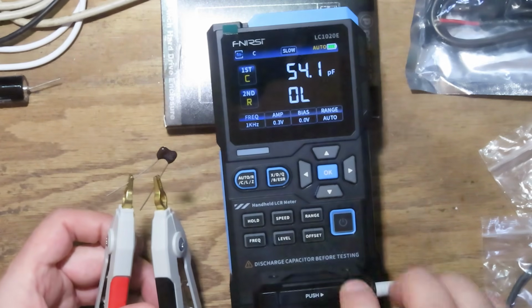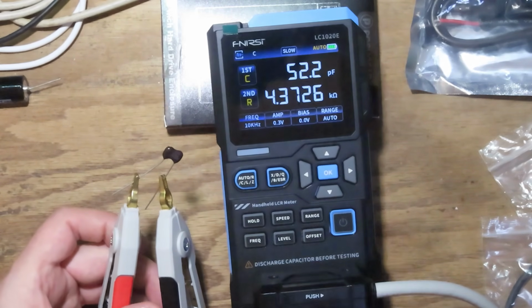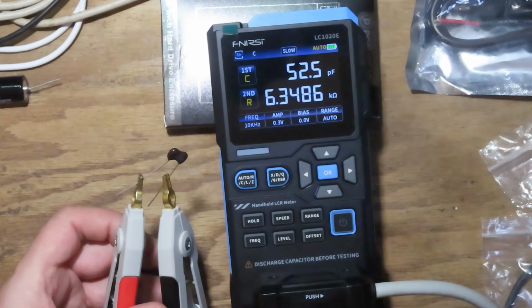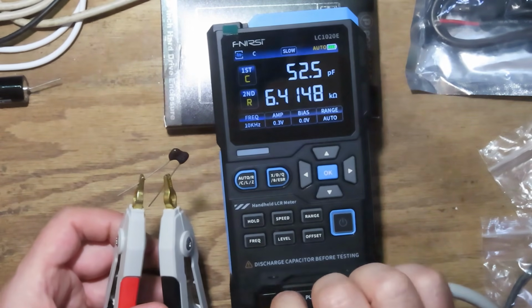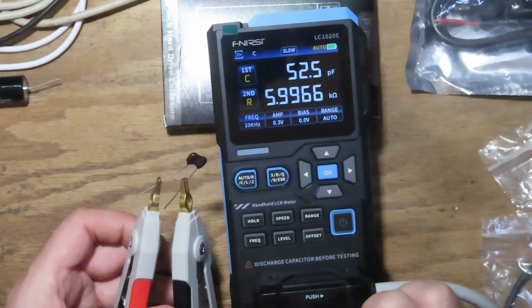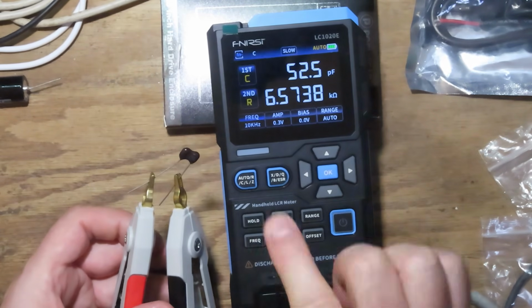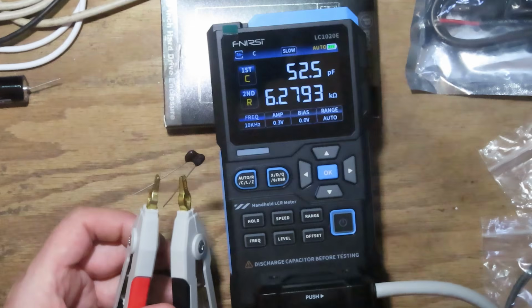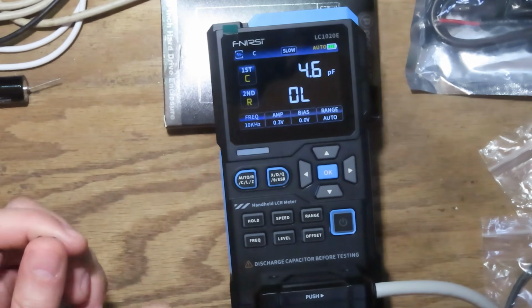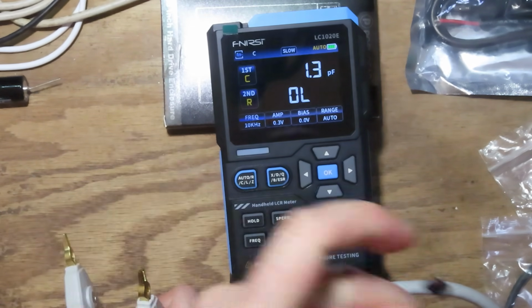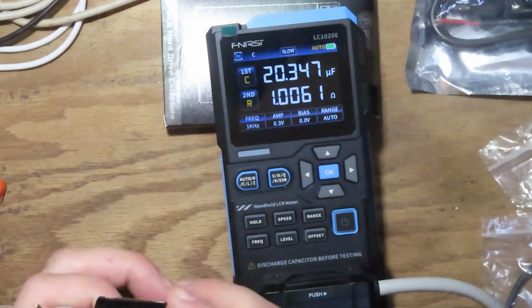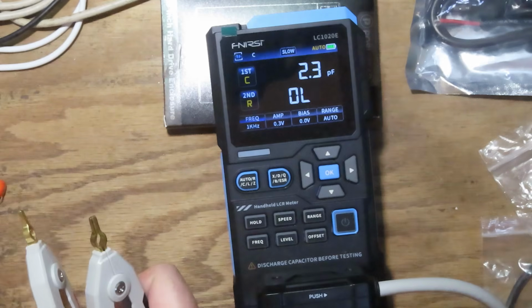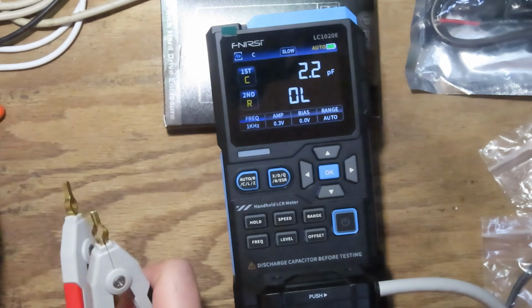We should go higher in frequency. Let's see if our reading changes. At 10 kilohertz, we're reading 52.5. According to our frequency guide, we should be at a higher frequency. So it's rated 51, we're reading 52.5 — that's fine. Of course, these guys don't age very much, so yeah, handy for checking out your capacitors.